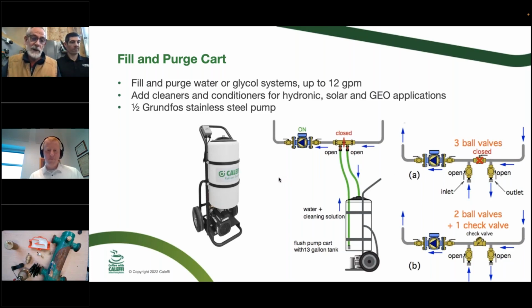blast that water out. I mean, you can use line pressure. You keep an eye on your pressure relief valve on your boiler, hook up a garden hose, and with 60, 80 pounds of pressure, you'll get a pretty good flush, but you've got to keep an eye and make sure that you don't pop your pressure relief valve on your boiler when you're doing that. So the bottom line is you just got to get a really good flow.